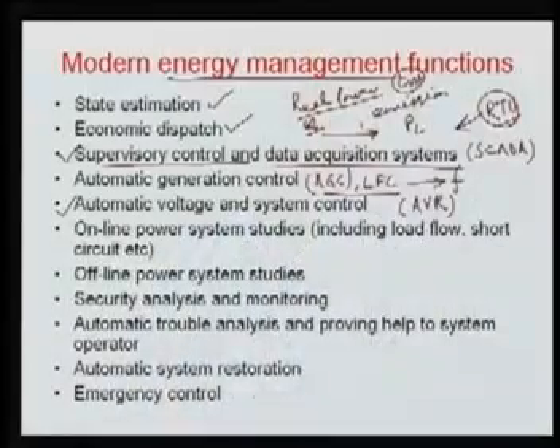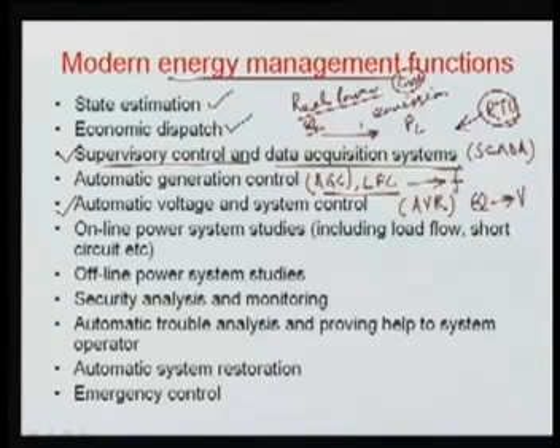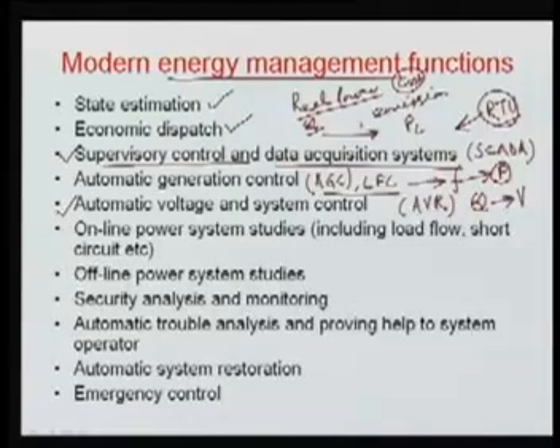We always know this reactive power is directly related to your voltage, whereas your frequency is directly related to your real power. So if you are changing the real power of a generator, you are changing the frequency of the system, whereas if you are changing the reactive power of the system, you are changing the terminal voltage. Vice versa, you can change the terminal voltage, and thereby the reactive power output of that generator will be changed. So in the automatic voltage control, we control the voltage of your generating units.